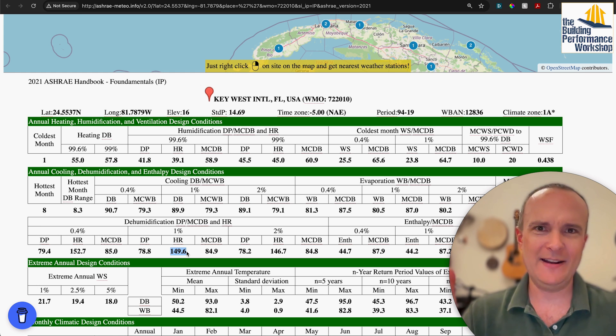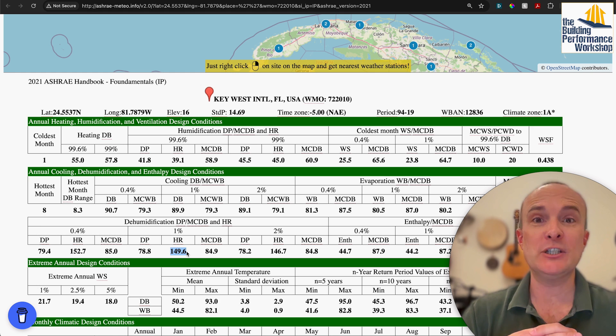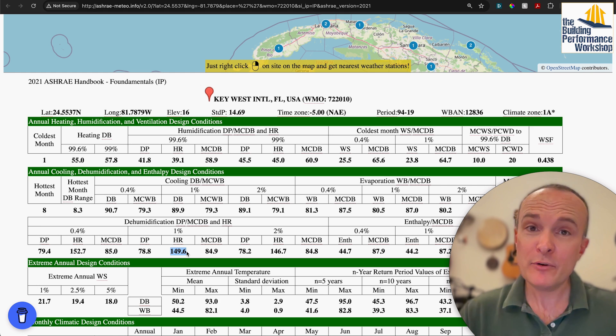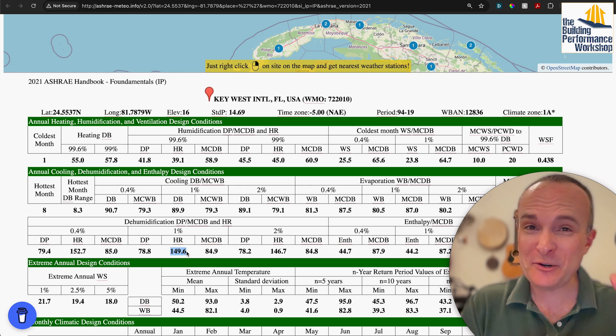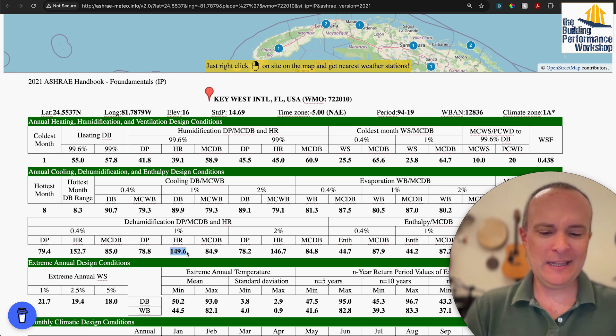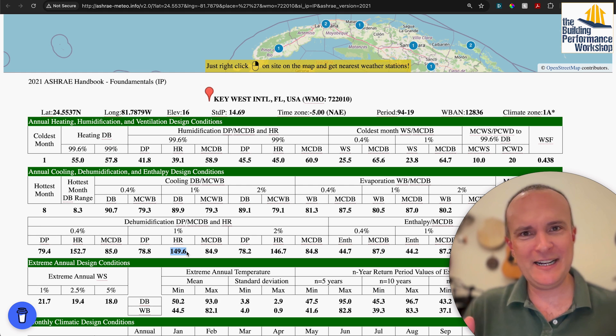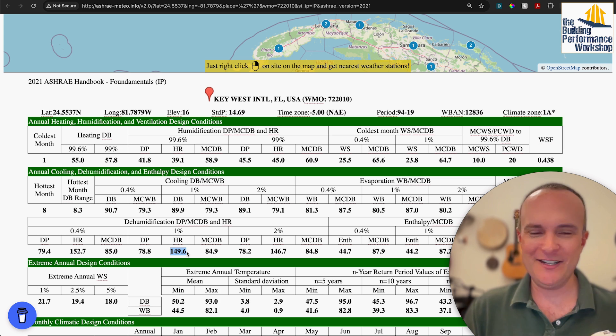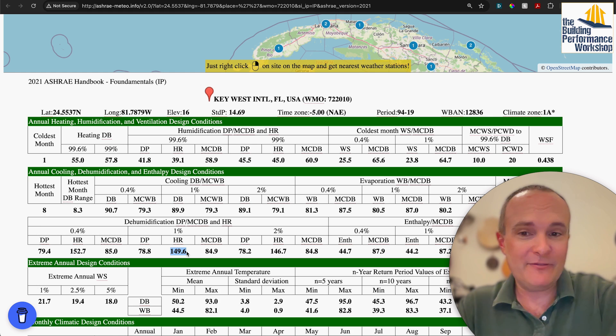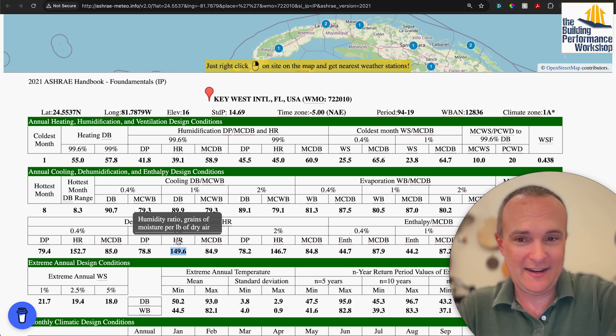A lot of people call me and say it's pretty humid outside but their house is super dry. I ask: what humidity is it outside? They say 90%. I ask the temperature, and they say 32 degrees Fahrenheit. That's actually super dry, because percentages of relative humidity are not the full picture — it only means how much humidity the air can hold. The humidity ratio — grains of moisture per pound of dry air — is what really matters.